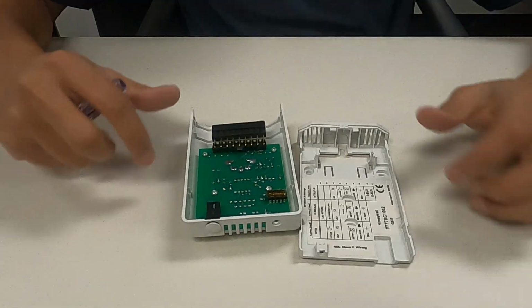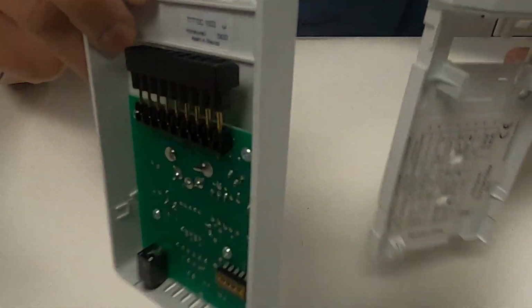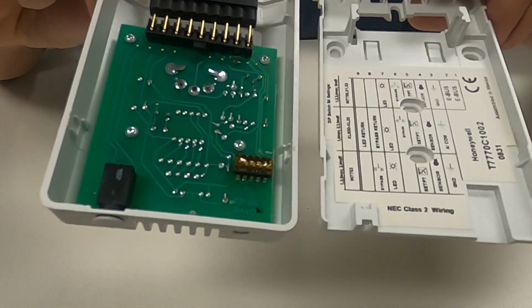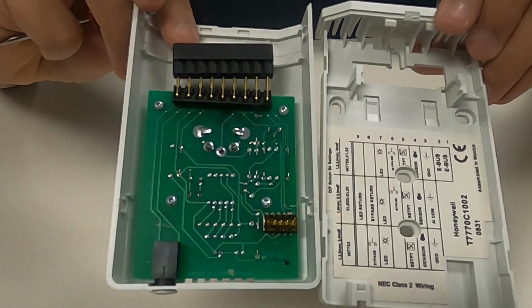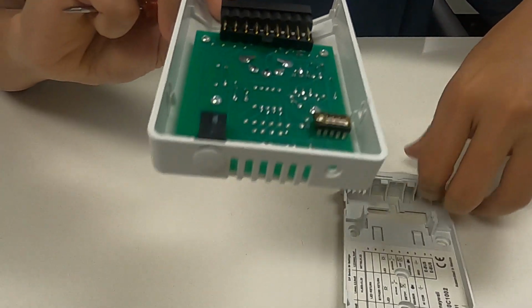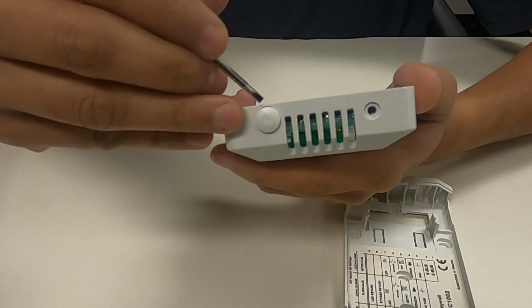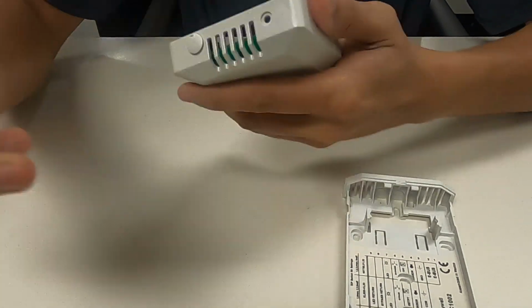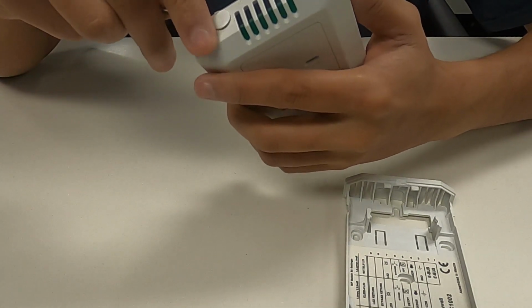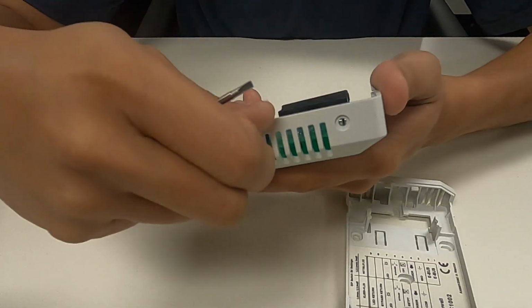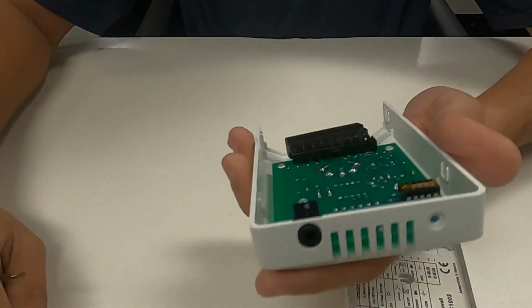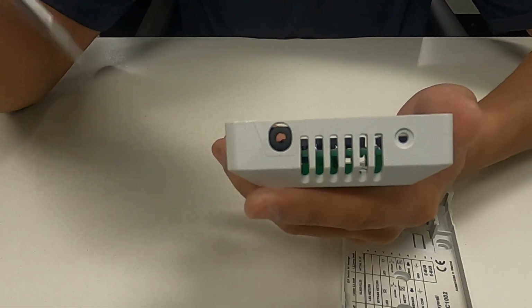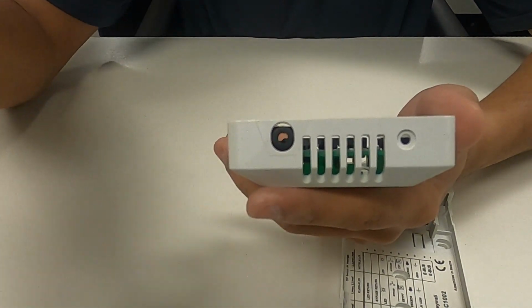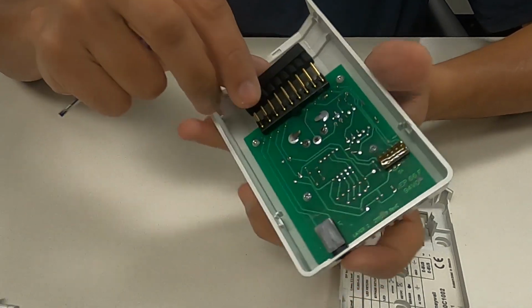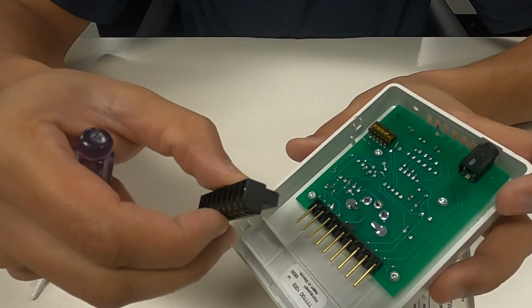Now, when it comes to wall temperature sensors, there are whole new types. There can be temperature sensors with a display, and temperature sensors without a display. There can also be temperature sensors with a display and a set point, which you can manually change from buttons or from a knob. The only difference is in the set points: you can use either a knob or buttons. However, it is based on your specification or your custom needs. It all boils down to that.